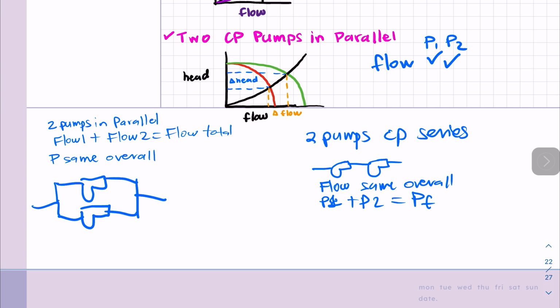So we have two pumps in parallel and two pumps in series. For parallel, we have the same pressure overall. For series, we have the same flow overall. That's the key difference. If we need to increase the flow in a system but keep the same pressure, we use pumps in parallel. If we want to increase the pressure while keeping the same overall flow, we use pumps in series. This lets us combine operations to meet requirements of high pressure with relatively low flow, or vice versa.